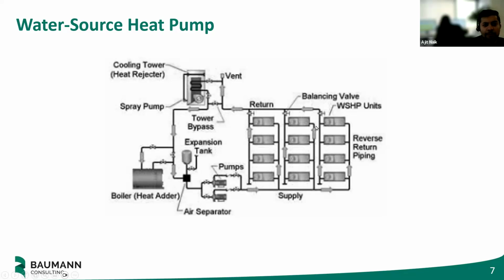So these systems usually have an operating range of like 40 degrees Fahrenheit up to about 90 degrees Fahrenheit, much more constrained than what you see outside in DC, where Lord knows we get those 110-degree days in the summer and those 15-degree days in the winter. So a water source heat pump allows the heat pumps to operate much more efficiently, because it maintains their temperatures, but we have this cooling tower, we have this boiler. These things also use energy, right? So they chew into a lot of the efficiency gains. While there are some efficiency gains to sharing the load, the cooling tower and boiler really eat away at a lot of those. And the boiler, for the most part, is gas, which doesn't do a lot for us. Our goal is to electrify and stop burning things in our buildings to meet our needs.